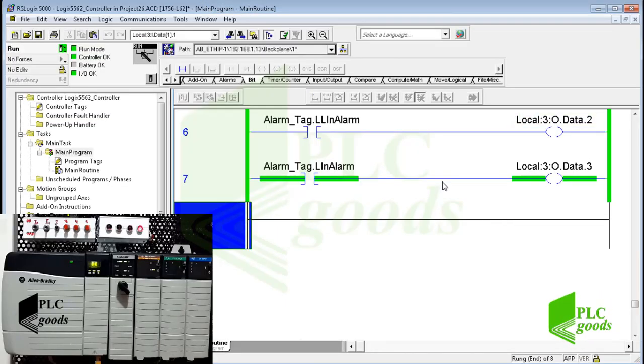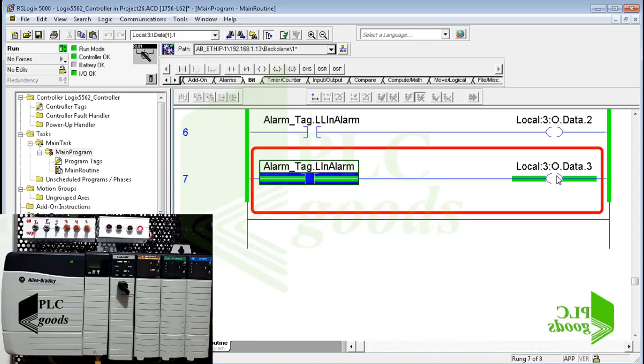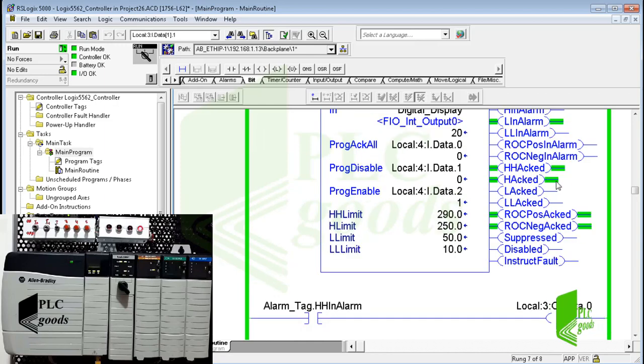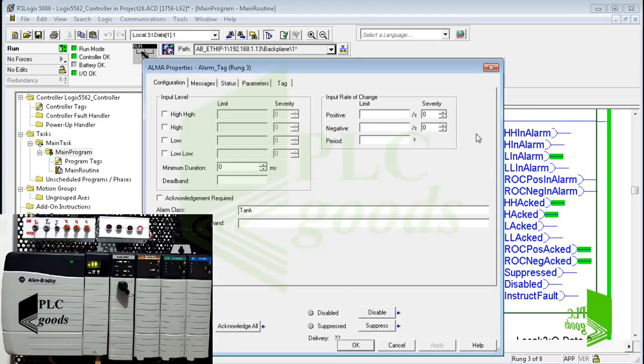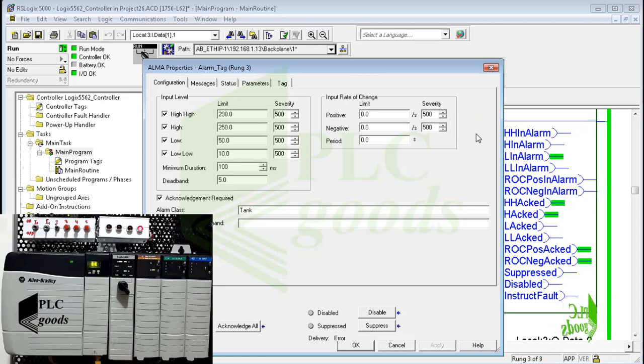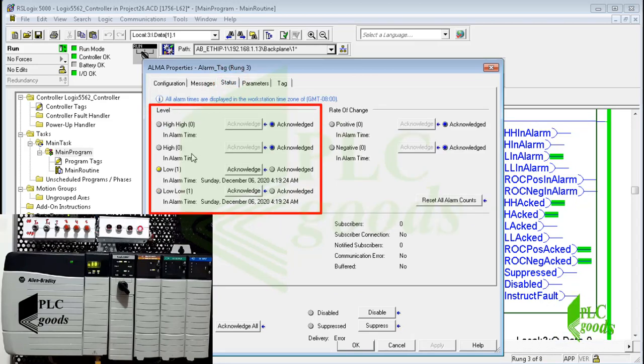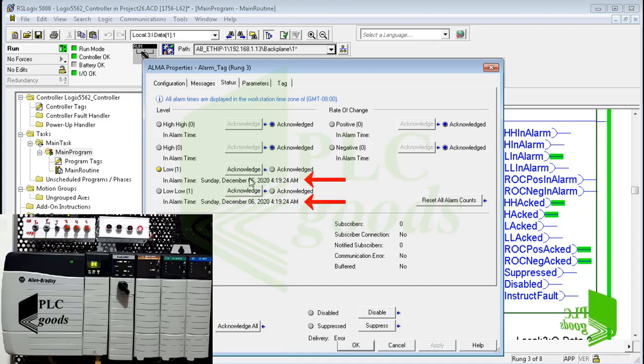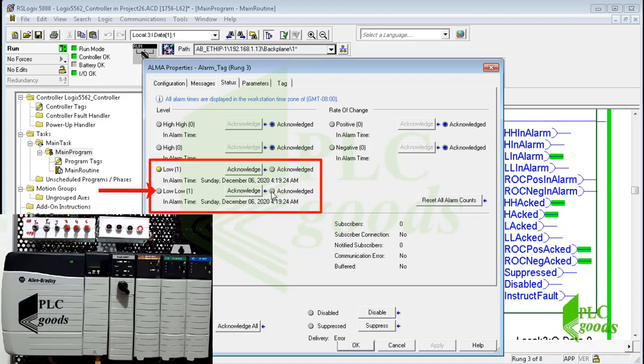Let's go back to the PLC program. As you see, only one alarm and output is activated. Let's open the alarm tag properties windows. Inside the status tab, we can see which alarm is activated and also when alarm conditions were detected. As you see, two new alarms have been detected. One of them has disappeared with the rising water level.